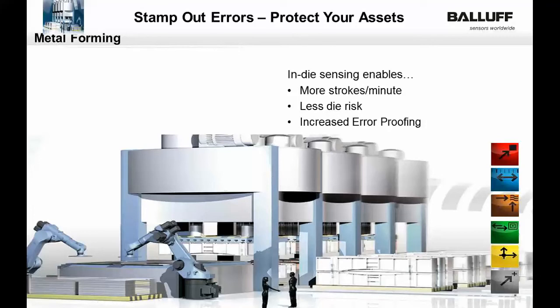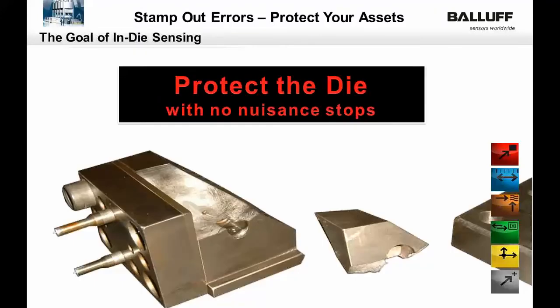So all of our customers need to ensure that they're having consistent quality product that they're able to ship to their customer, and to reduce the amount of flaws in the finished product that they're producing. So not only do we want to ensure that we're having effective error proofing, but we also want to ensure that we're not having nuisance stops or false calls. We don't want the press to shut down when there's actually not a fault. So it's important that we choose the right sensing device for the right application so the customer is realizing full potential out of their investment.